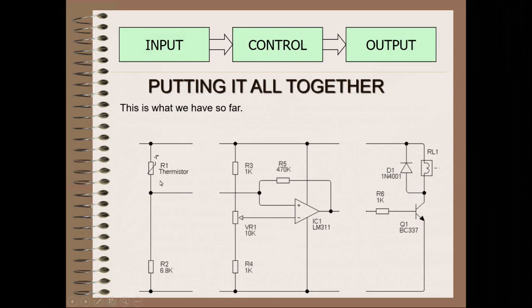So this is what we have so far. You have your input coming from the thermistor, and it's the voltage divider network. Temperature causes the resistance of the thermistor to fluctuate. Then you have the control, which is your variable resistor that establishes your set point where you desire your temperature to be. The difference between the thermistor's resistance and the variable resistor's resistance ultimately will determine the inputs to the comparator. The comparator is comparing the voltages that result from these two voltage divider networks.